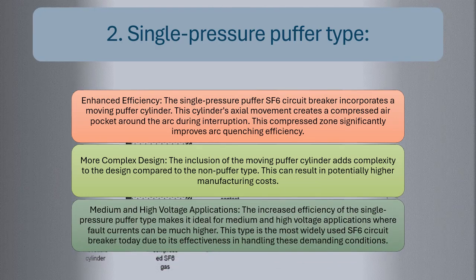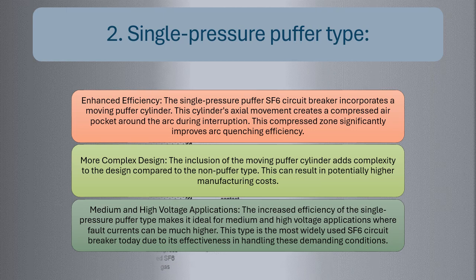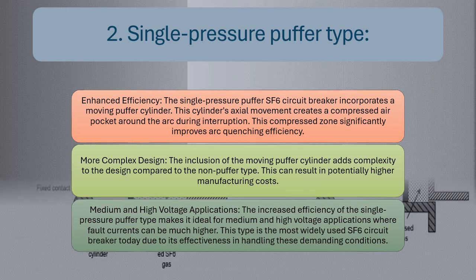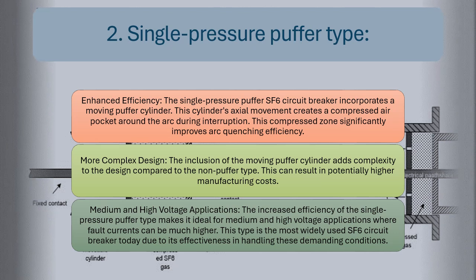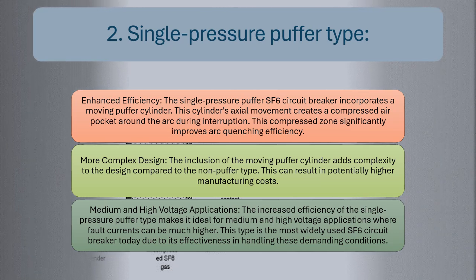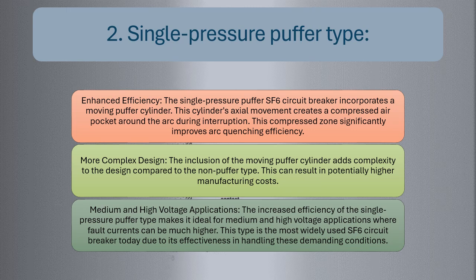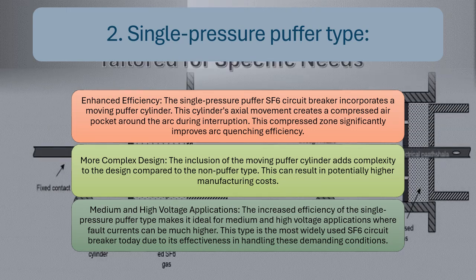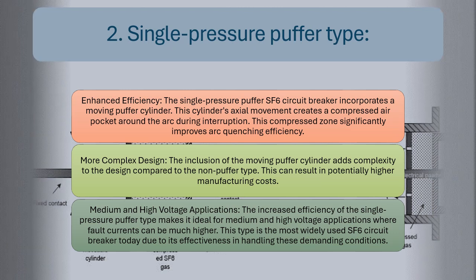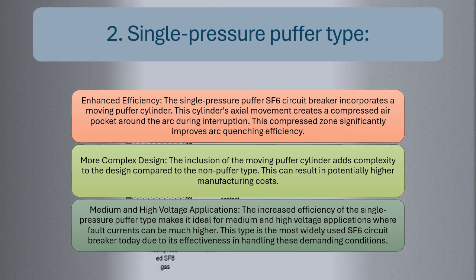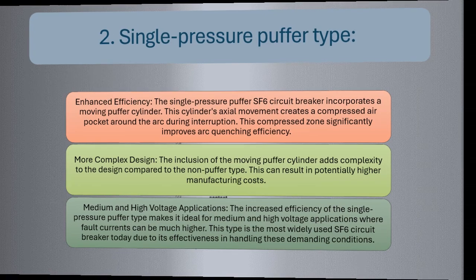It's suited for medium and high voltage applications. The increased efficiency of the single-pressure puffer type makes it ideal for medium and high voltage applications where fault currents can be much higher. This type is the most widely used SF6 circuit breaker today due to its effectiveness in handling these demanding conditions.